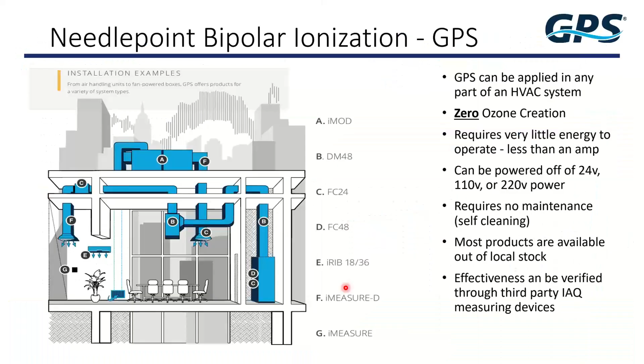Those needles on these guys need to be cleaned every couple months, just basically wiped off. Some of the manufacturers, like this one here, have put little, I'm going to call them helicopters, on there, with a little tiny servo motor, and once a day that thing just spins, click, click, and basically knocks off debris off the tip of those bristles. So it's self-cleaning, if you will. So the negative is you have a moving part, which means 10, 12, 15 years from now, you might have to change it out. The positive is I don't have to go to this device every month and manually knock debris off the brushes. Because once those things are charging, right, positive and negative, other things in the air might be sticking to them.